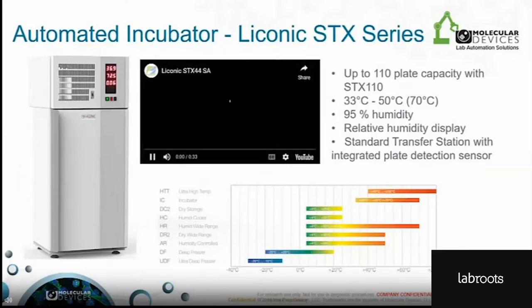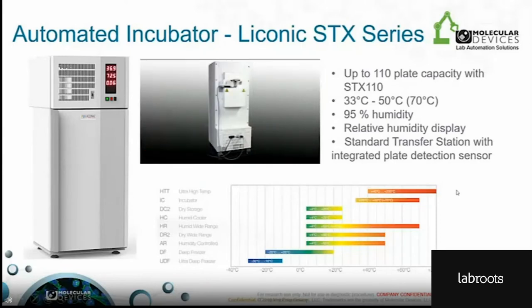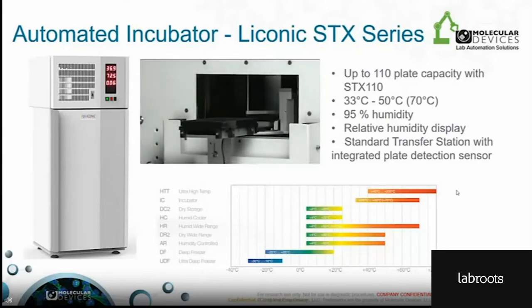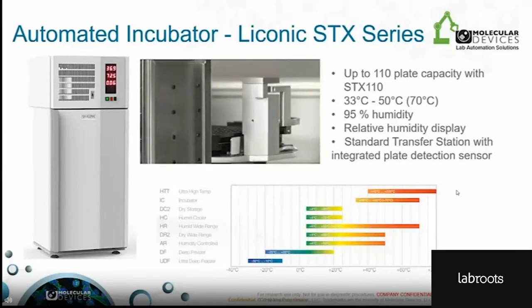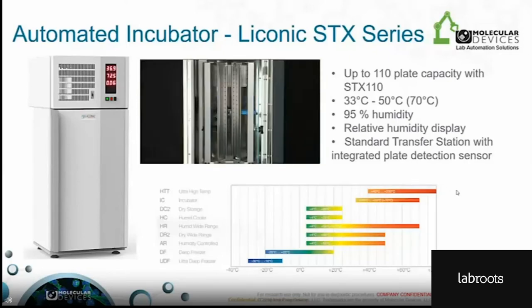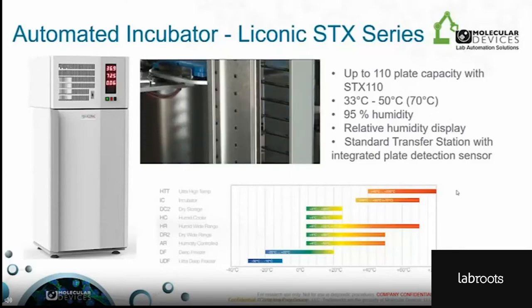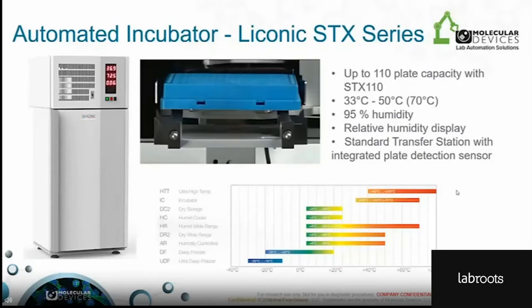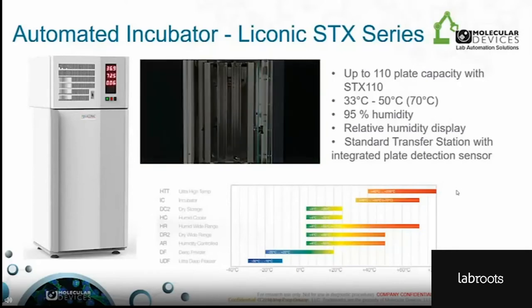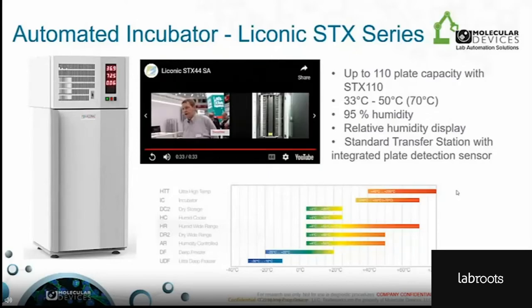Automated work cells can include automated incubators to assist in providing environmental control. The Liconic STX series automated incubator provides a complete solution for controlled environmental automated storage for integration into a work cell. We partner with Liconic as the STX line is the most widely used and complete solution for controlled environmental automated storage in laboratory automation. The relatively small size makes them suitable for small-scale integration, miniaturized applications, and short or long-term incubation assays. The STX series offers climate options accommodating temperatures as high as 70°C and a maximum humidity of 95%, with barcode reading also possible.